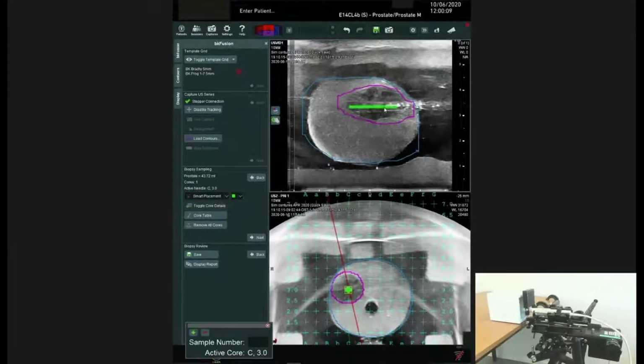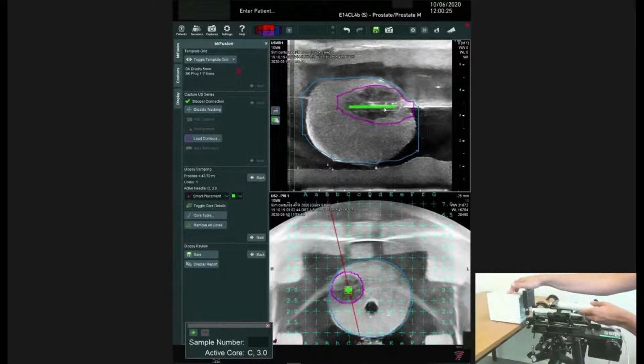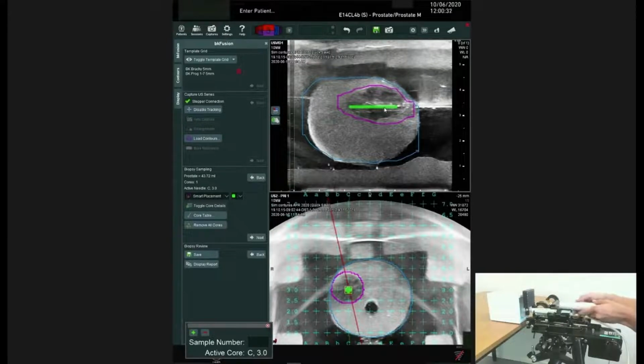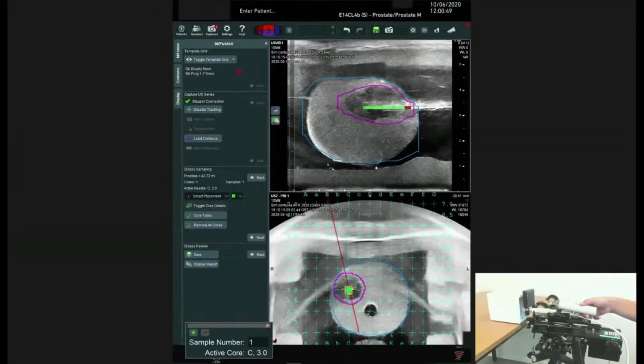The next step will be to prepare the biopsy needle and the biopsy gun. When ready, the biopsy needle is now introduced into the C 3.0 hole on the grid. You can now see the needle entering from the top right of the screen, and it will be stopped just prior to the target. Then the biopsy gun is fired, and next you will document where the biopsy was taken by placing the marker over the location. This is done by selecting and holding the select key down and moving the trackball on the keyboard. You can see that there is now a red portion on the marker, indicating that a sample has been taken from this location.